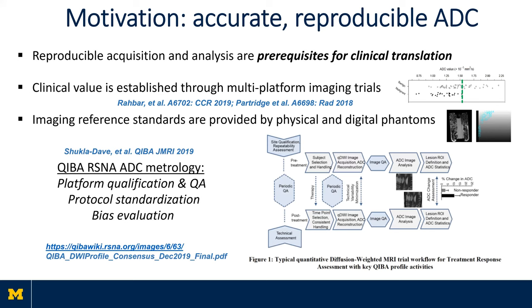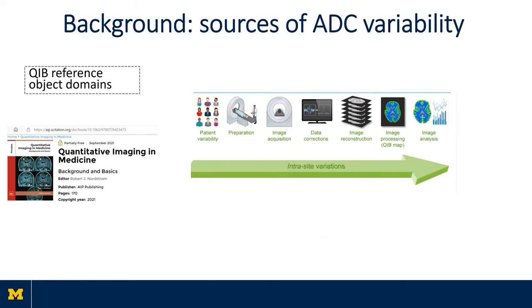QIBA RSNA's ADC profile now includes recommendations for phantom use as an integral part of clinical trial workflow, including platform qualification, periodic QA, and performance evaluation. Based on our experiences, we contributed a chapter to a quantitative imaging network book recently published by AIP, devoted to the role of phantoms for characterization and reduction of technical variability in quantitative imaging biomarkers.